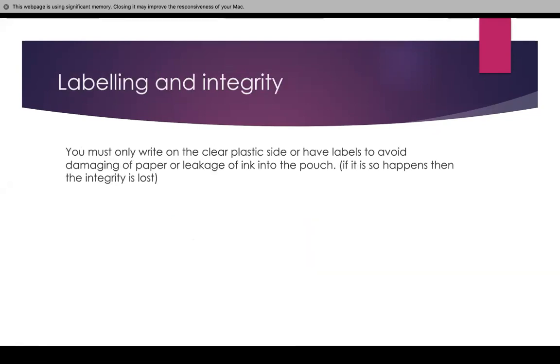You must write on the clear plastic side or use labels to avoid damaging the paper or allowing ink to leak into the pouch. If this happens, the integrity is lost. Any labeling cannot be on the paper side because once you put it in the sterilizer, you have heat, water, and pressure and the ink will leak inside. The plastic will contain it, so write on the plastic side and not the paper side.